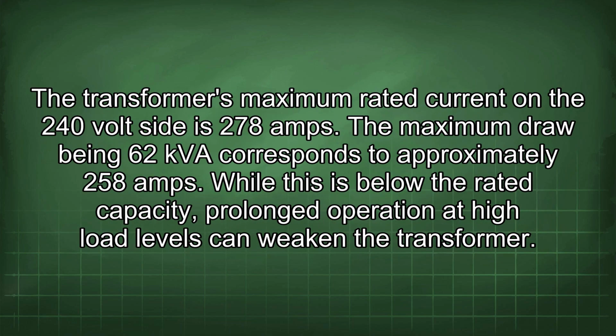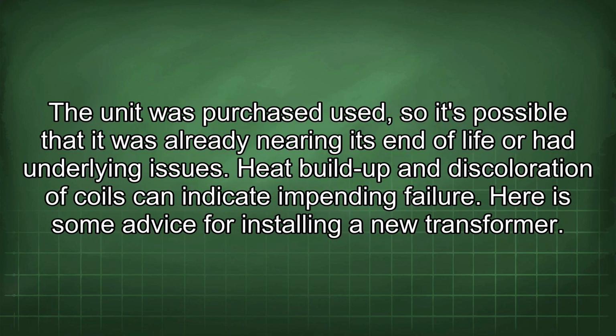The transformer's maximum rated current on the 240 volt side is 278 amps. The maximum draw being 62 kVA corresponds to approximately 258 amps. While this is below the rated capacity, prolonged operation at high load levels can weaken the transformer. The unit was purchased used, so it's possible that it was already nearing its end of life or had underlying issues. Heat build-up and discoloration of coils can indicate impending failure.